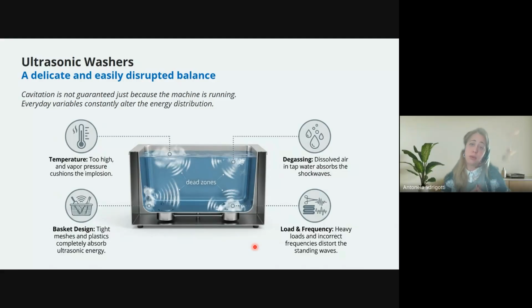And the incorrect performance of the transducers, not at the right frequency, will also be detrimental for the cavitation energy. As I have mentioned, temperature too high will create vapor pressure, and this will destroy these cavitation bubbles. And of course, the basket design and material, okay? Not every material is compatible with an ultrasonic washer working with the right energy.